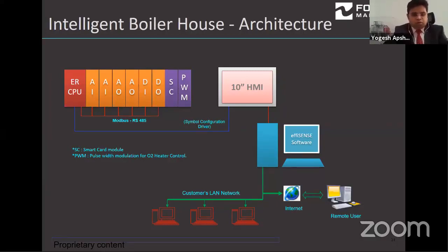So this is how the architecture of the intelligent boiler house looks like. We take the signals from the hardware installed on the equipments, which give the signal to the centralized HMI, and the HMI is giving a signal to the central processing unit. And this is the software which we have, Effisense or Eversense software, in which you can monitor all the important parameters of the boiler house on a simple screen. And then you can share this to the customer LAN network. And if we have web connectivity for this software, then even remote users can see this, or the people sitting back in India or back in Germany or anywhere else in the world, they can always look at this data remotely and they can give the inputs.